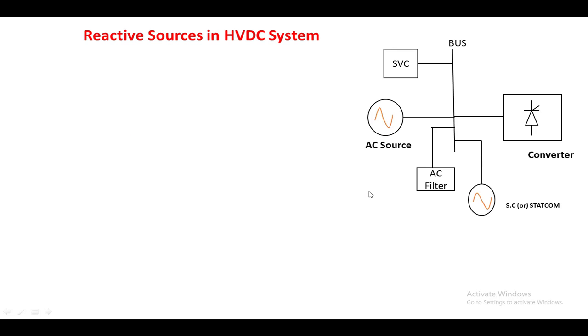This is the layout of the HVDC transmission system, showing the AC source, the bus, and the converter. The AC filter is used to filter out harmonics in the source current. This AC filter can also supply reactive power to the bus for small load variations. The SVC, or static VAR compensator, can supply reactive power to the bus for large load variations.